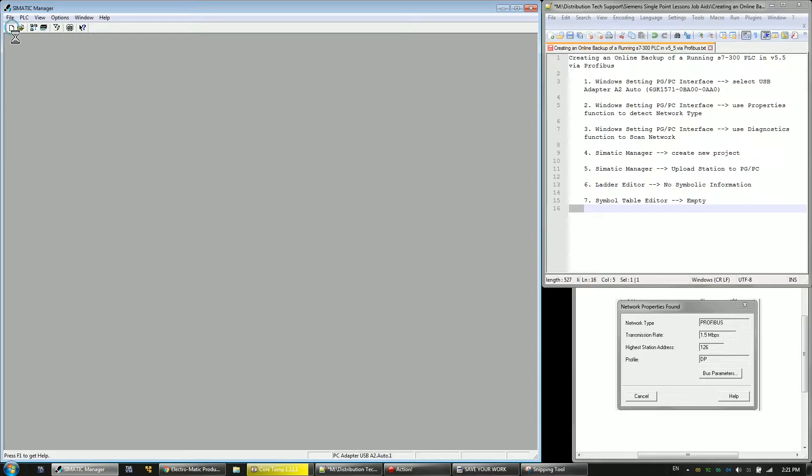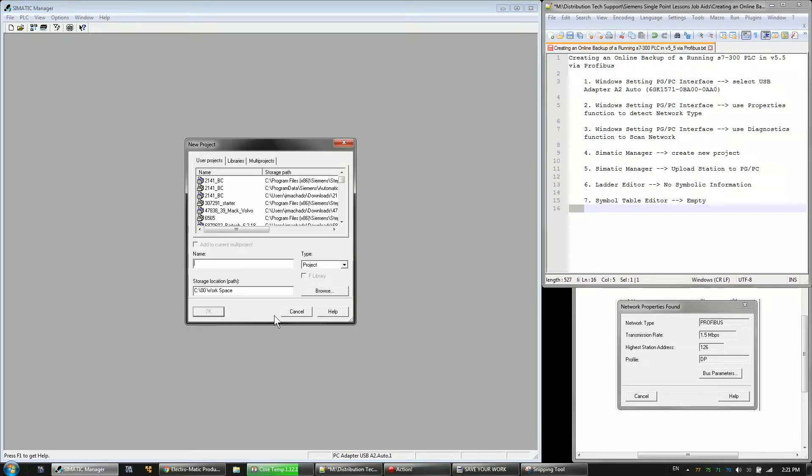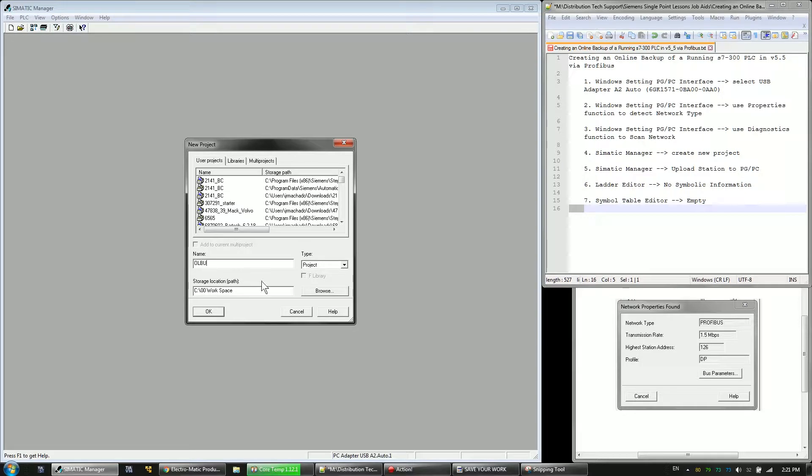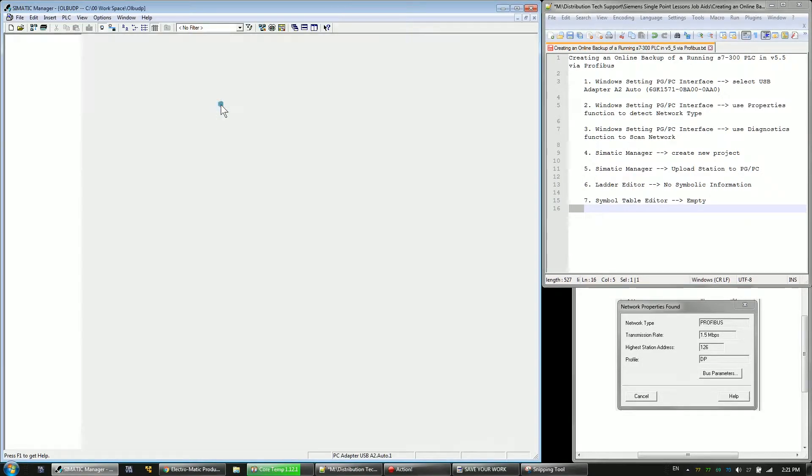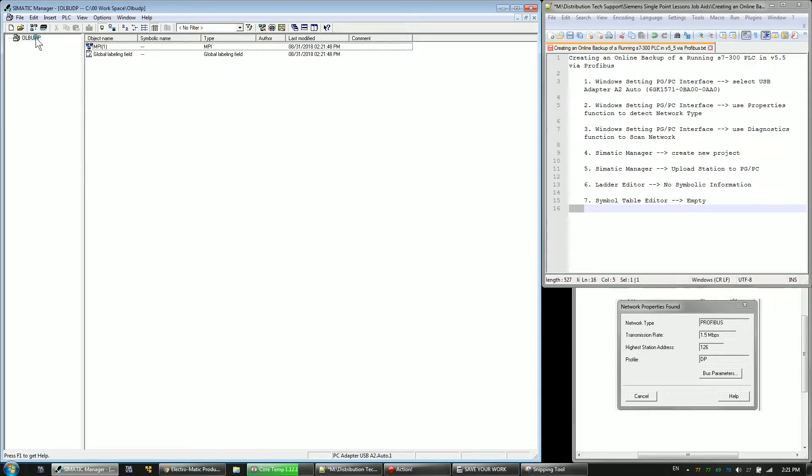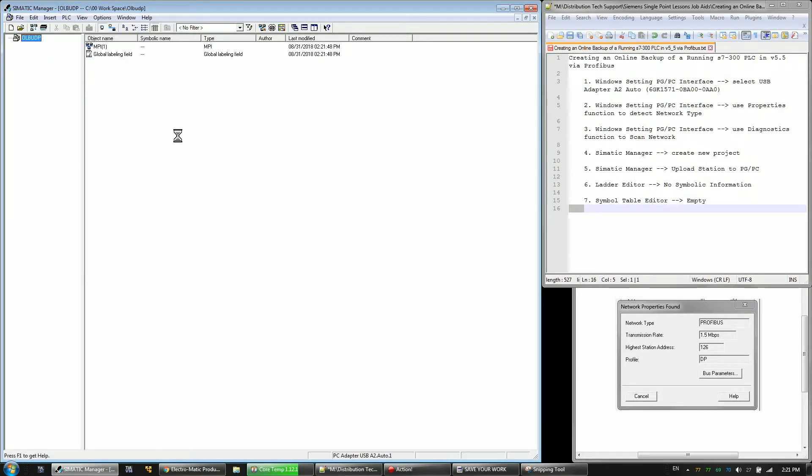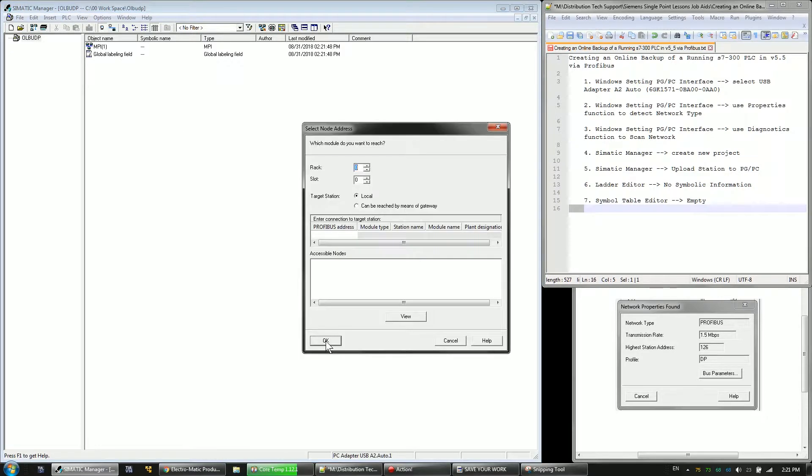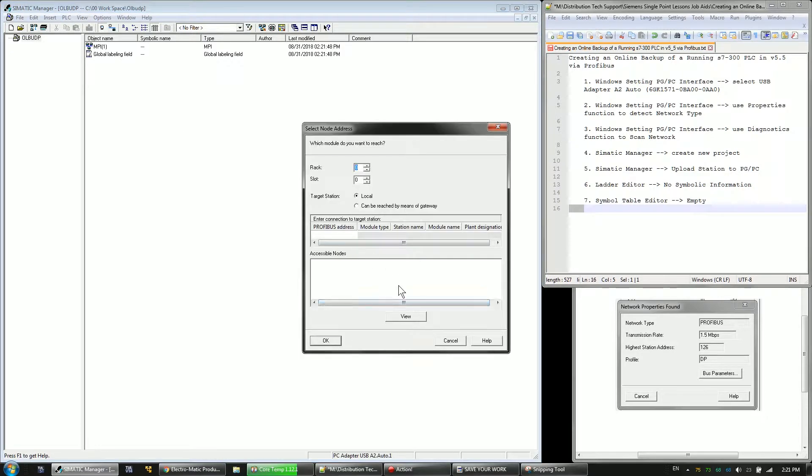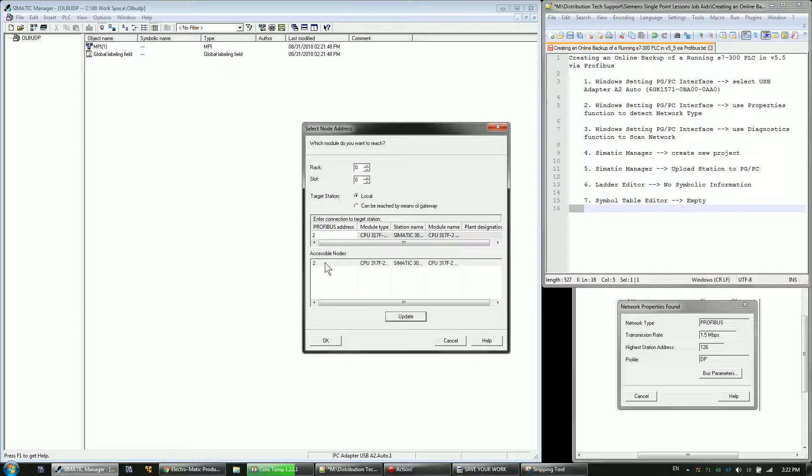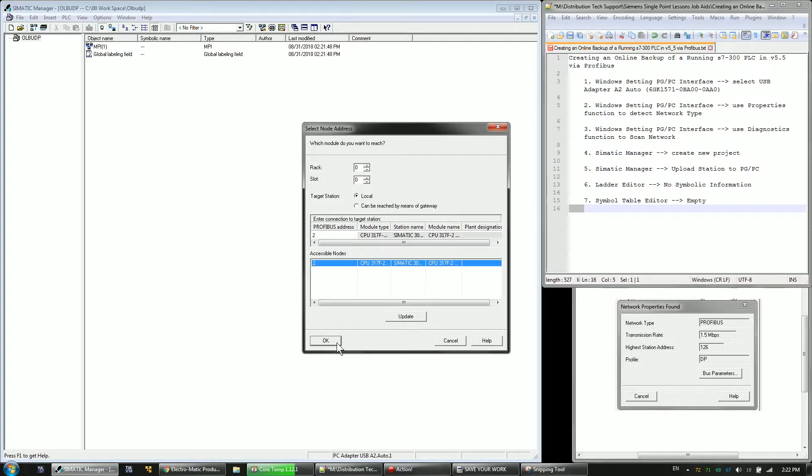All right, so the first thing I'm going to do is create a new file and I'll just name this online backup. All right, so I won't add anything to this. I'll just go to PLC, upload station to PG, and I'm going to scan the network here to find my PLC. It's address two. So I'll click on that, click OK.